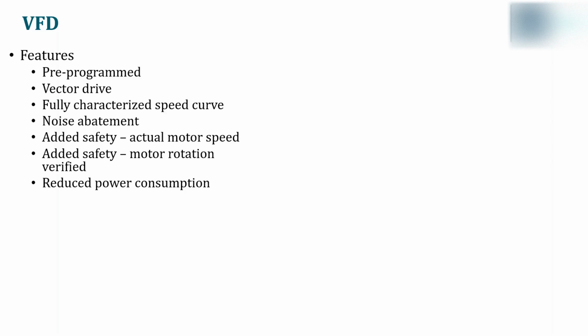Now, one thing I'd like to point out is all the drives that are purchased from SCC are pre-programmed at the factory prior to shipment. It's really nice in the sense that once you get the VFD, all you have to do is wire it up, install it, and it's done. All the drives are vector drives. With the VFD, you're allowed a fully characterized speed curve. You have noise abatement. You have additional safety in terms of actual motor speed, and additional safety in that motor rotation is verified. And finally, you get reduced power consumption.